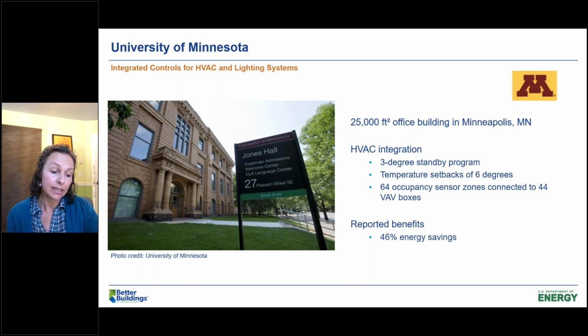Their upgraded LED system with luminaire level lighting controls allowed them to not only fine-tune the light levels in the building to meet the needs of the occupants, but also provided the ability for demand control ventilation, thermostat setbacks of 6 degrees, VAV shutoff, and supply air temperature resets, which has reportedly saved 46% of the total HVAC system energy.